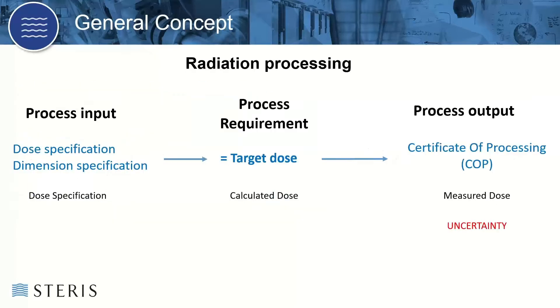In radiation processing, we have a process input — which is really the dose specification and the dimension specification — meaning we want to make sure that the validated state remains after the PQ, so the box sizes aren't changing from the way we validated during PQ mapping. We have a process requirement, which is the target dose. And then we have a process output, sometimes called the certificate of processing. This is the measured dose, and the measured dose has an uncertainty associated with it.